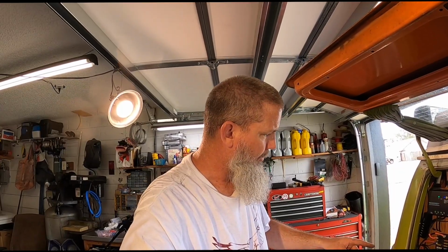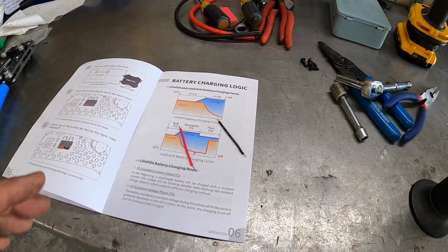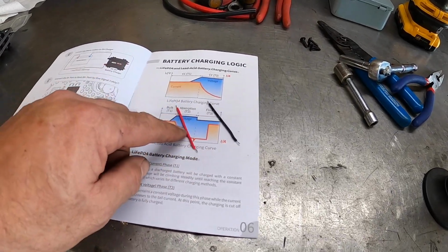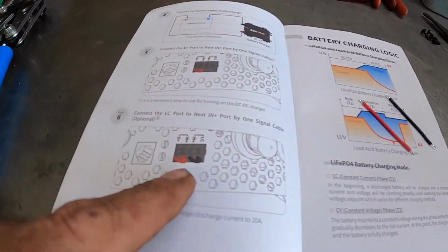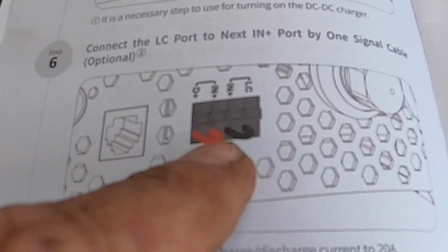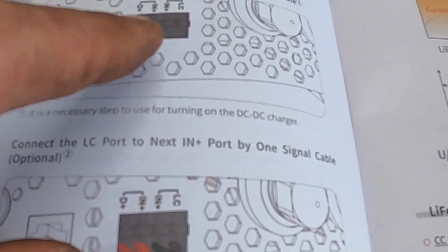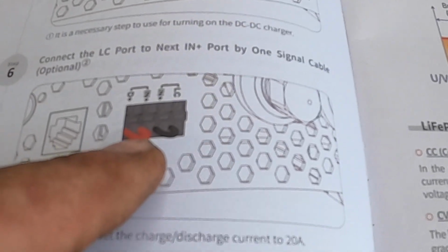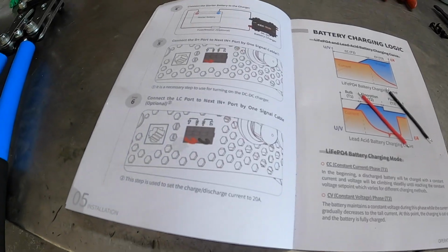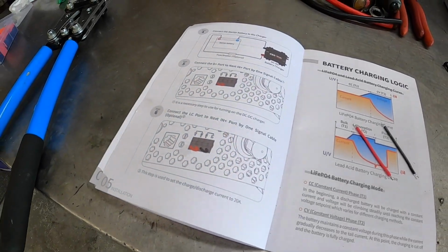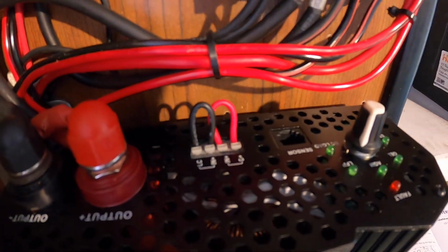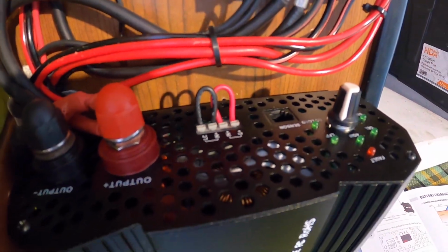Now we need to go ahead and put the little jumpers in line, so instead of charging at 40 amps, it'll charge at 20 amps. Let me show you that. In your kit, it comes with these two little red and black jumper wires, and right here in the kit it shows you exactly how to do it. So we'll run the wires in just like that, loop them around, and that takes us from a 40 amp charge to a 20 amp charge. And just like that, our jumpers are installed.